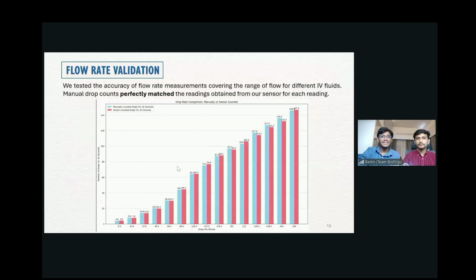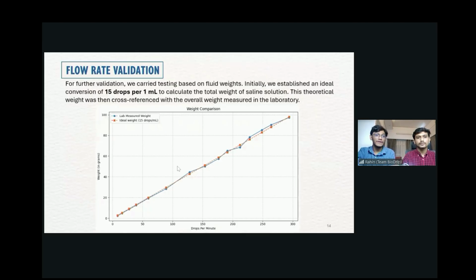Now moving to validation, we tested our drop counting accuracy across the full clinical range. Manual counts and sensor readings matched perfectly across every tested flow rate. We further validated the results using fluid weights, applying a standard 15 drops per milliliter conversion according to our national dengue guideline. The lab measured weights showed near perfect collinearity with theoretical values, confirming volumetric accuracy as well.